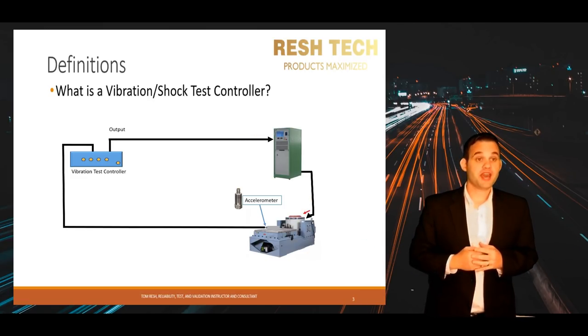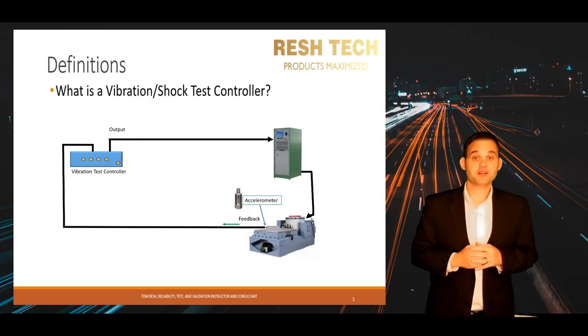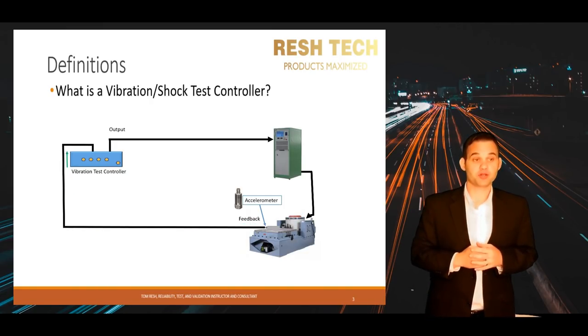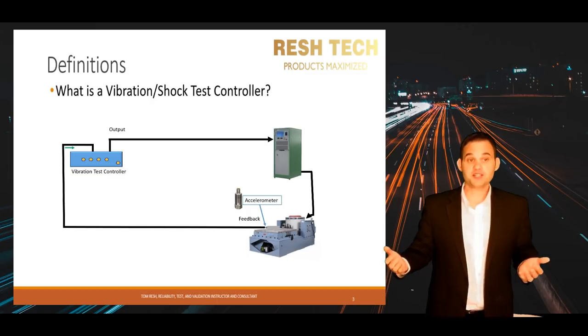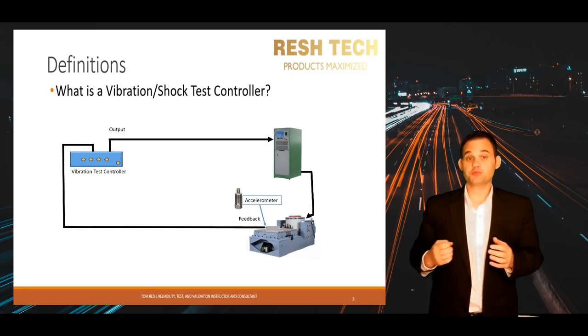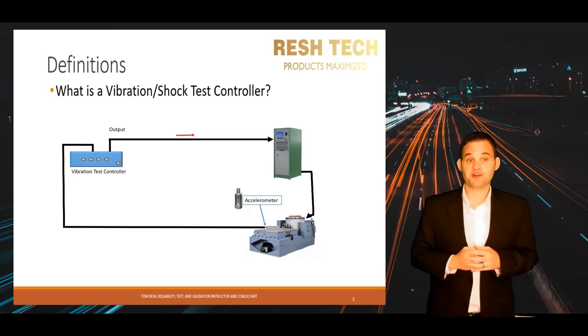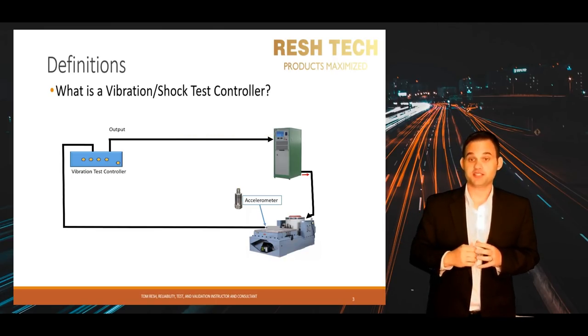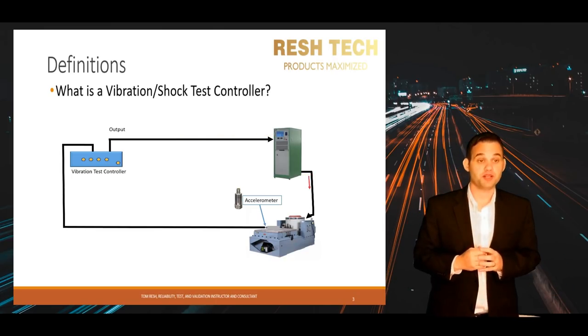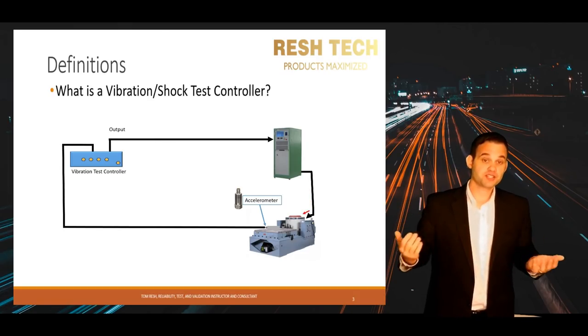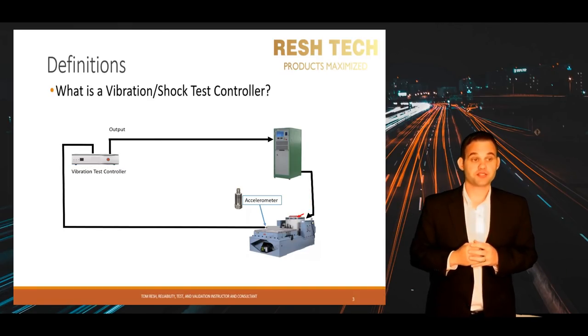Here we see a vibration and shock test controller, an amplifier, a vibration test system, and an accelerometer. The signal is outputted from the vibration test controller based on your profile. The amplifier amplifies the signal and the vibration test system produces a mechanical output based on the electrical input signal, just like your stereo system.